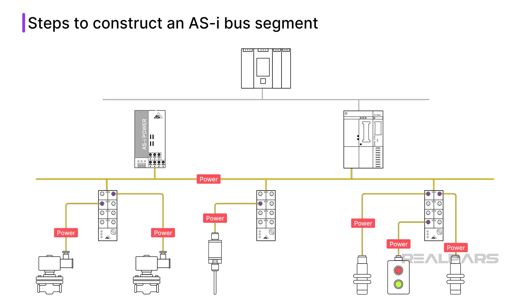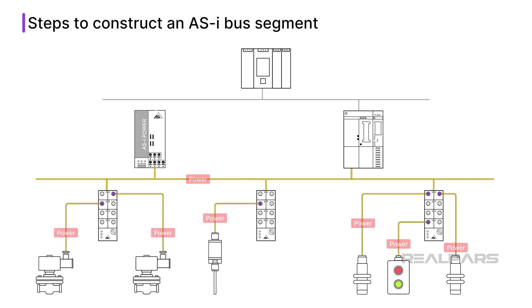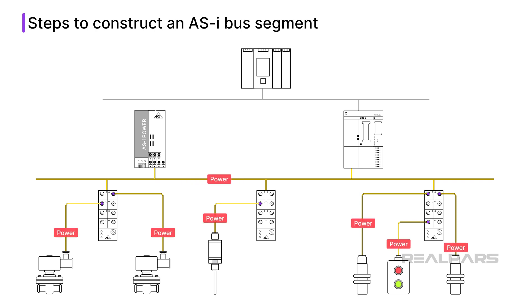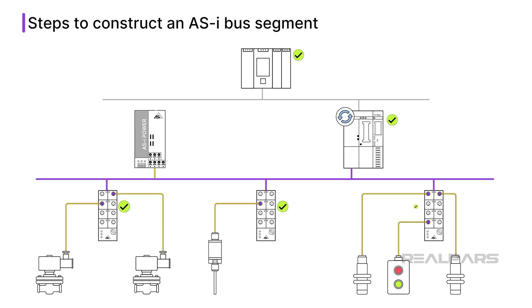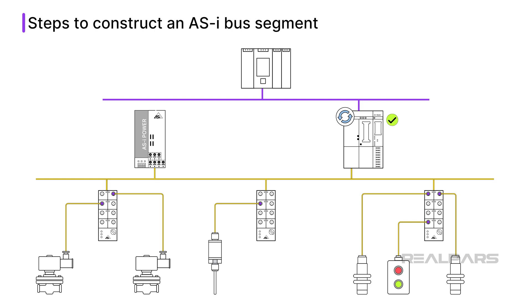I power on the segment and ensure that all of my field devices are receiving power. I see some error lights on the devices, but that occurs because I have not yet configured all of the nodes in the master. I need to tell the master which nodes should be present. I also need to configure the communication to the PLC or DCS that the master is connected to.